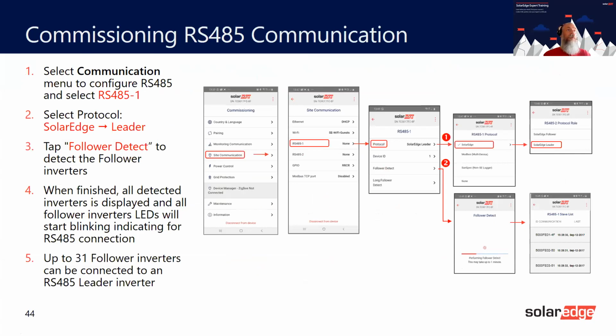For RS485 communication, you would go to site communication, and you've got on here Ethernet, Wi-Fi, RS485 1 and 2, and then you've got your GPIO, which is basically controlling the inverter remotely, and then you've got your Modbus TCP port, also for using SunSpec protocol and things like that. And you just choose follower or leader, or you choose you want a meter. This particular picture shows how we would do the follower detect, and then you get your slaves here. They would pop up.